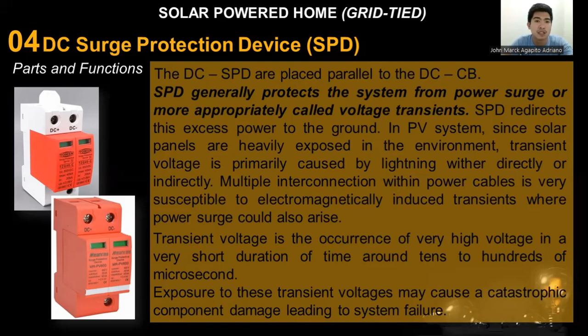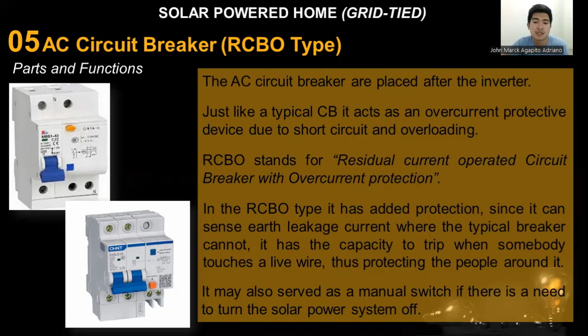Next is the AC circuit breaker, RCBO type. Parts and function: the AC circuit breaker is placed after the inverter, just like a typical CB it acts as an overcurrent protecting device. It is a protective device against short circuit and overloading. RCBO stands for residual current operated circuit breaker with overcurrent protection. It may also serve as a manual switch if there is a need to turn the power system on or off.